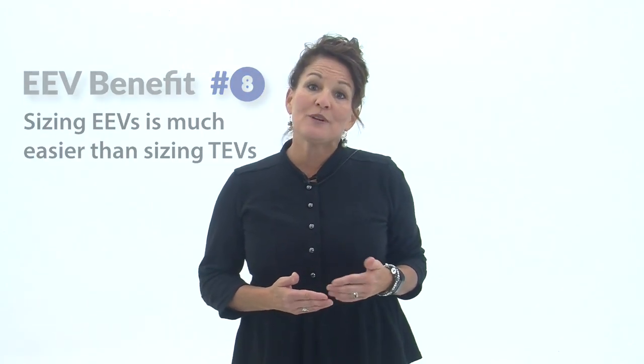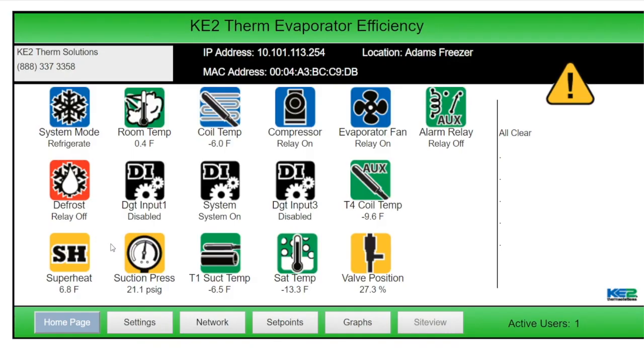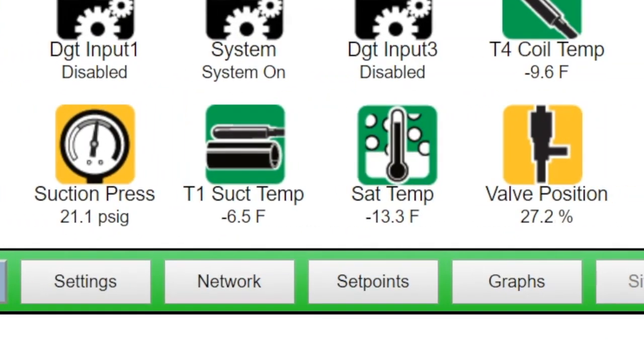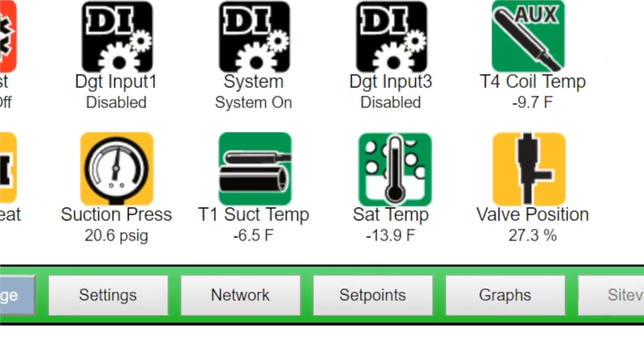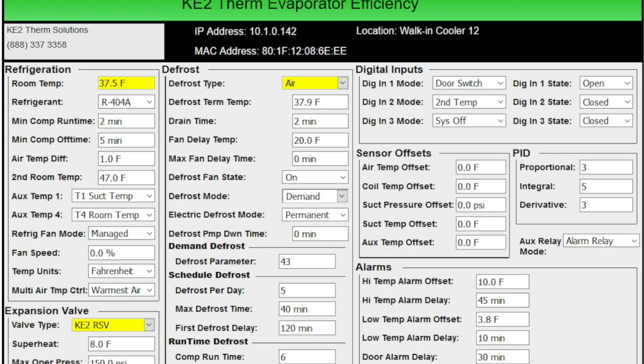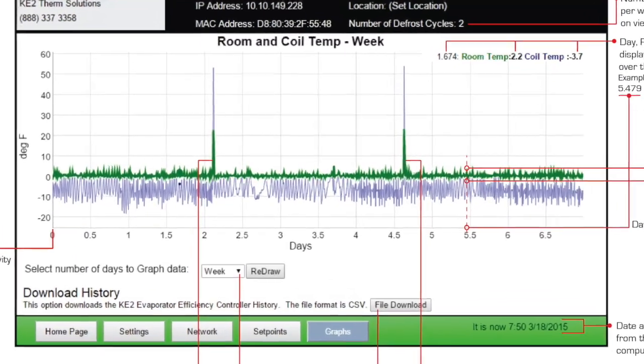The most common mistake we see is EEVs being sized too small. Finally, with the KE2 Therm controller managing your system, you have communication compatibility with the EEV. You can remotely monitor superheat, suction pressure, temperature, valve position, and a bunch of other important data. You can also adjust set points and access performance history, which is critical for system diagnostics.